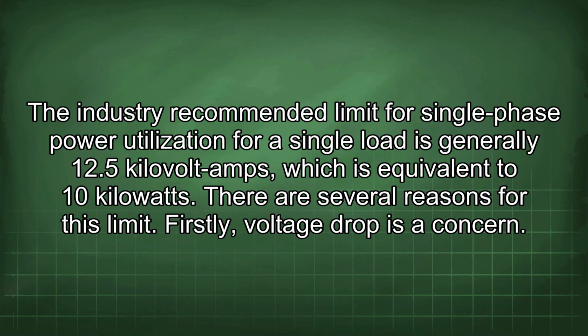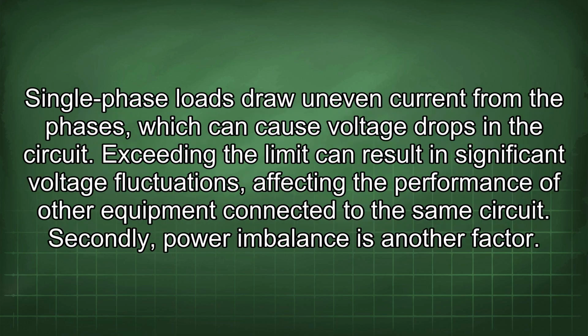The industry recommended limit for single-phase power utilization for a single load is generally 12.5 kilovolt-amps, which is equivalent to 10 kilowatts. There are several reasons for this limit. Firstly, voltage drop is a concern. Single-phase loads draw uneven current from the phases, which can cause voltage drops in the circuit. Exceeding the limit can result in significant voltage fluctuations affecting the performance of other equipment connected to the same circuit.